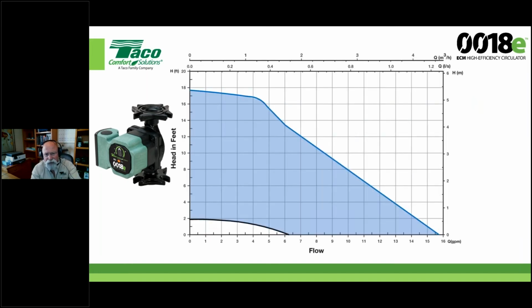This is what it looks like without all those little performance curves at reduced RPMs. But let's go in. We need 10 gallons a minute. And we estimated about 5 foot of head. That's calculating a system curve, or a resistance curve, for this to be something like that. That gives me an operating point that's beautiful. I even got room to go up, but more importantly, I got room to turn this thing down. And again, we'll turn it down when we get the feedback from the boiler manufacturer that gives us the delta T under a design load condition.